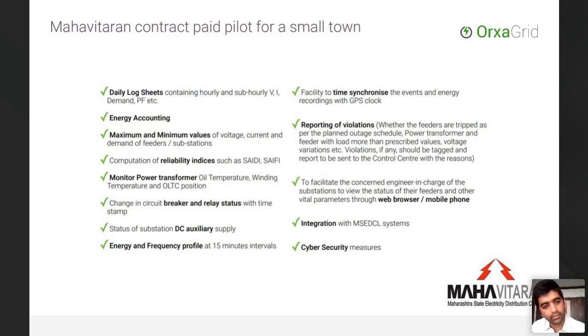Then energy and feeder profiles, yes. Facility to time synchronize. So we do time synchronize the data center server with the GPS server, and then each of the sensors is in turn synchronized with the central software, very similar to how typical RTU and SCADA control center deployments happen. Moving on, again, of course, reporting of violations through emails and SMS, like I mentioned, and then finally, we also have complete open APIs for integrations with other MSEDCL systems, which can come into place, and cybersecurity was also ensured through encryptions.